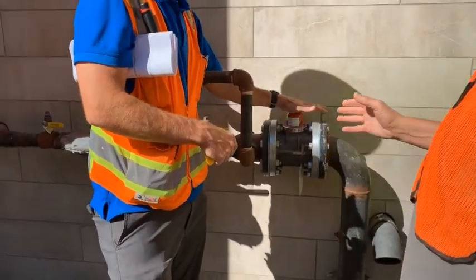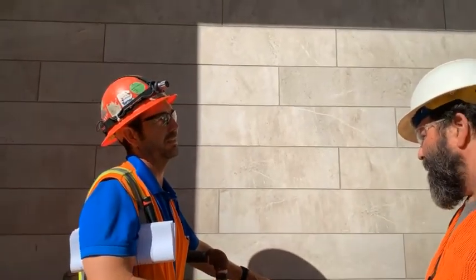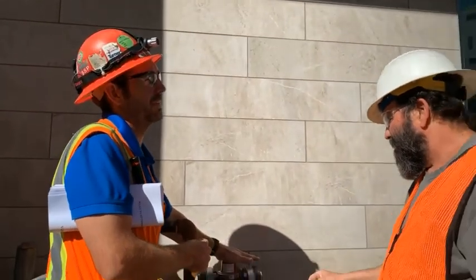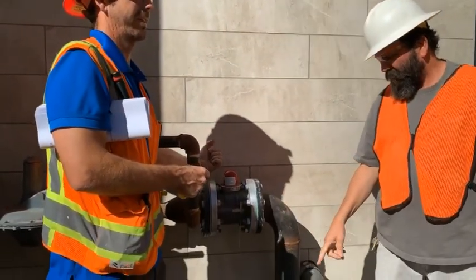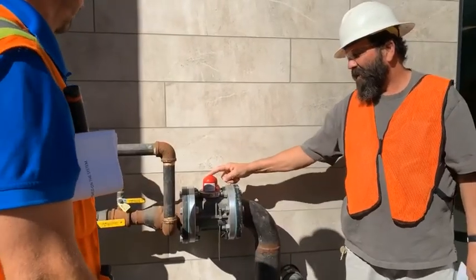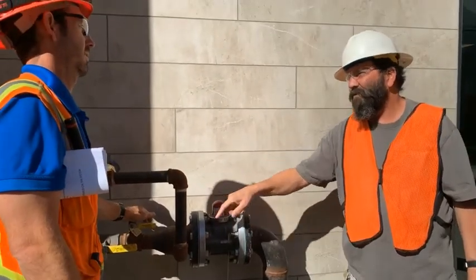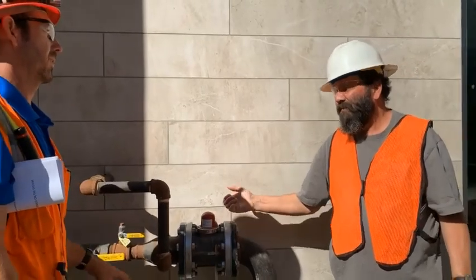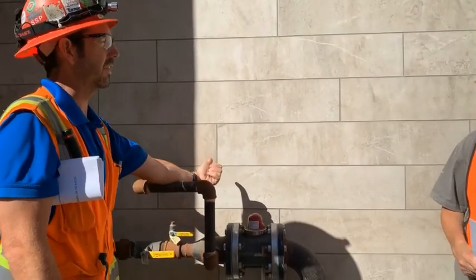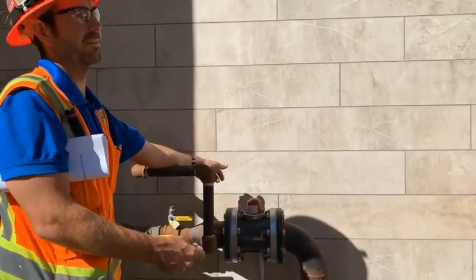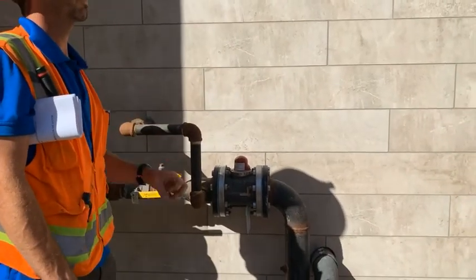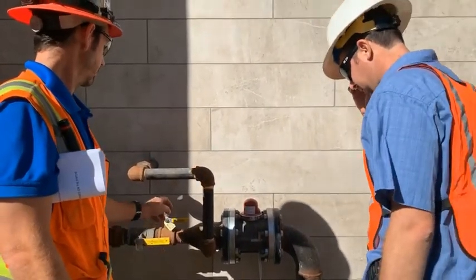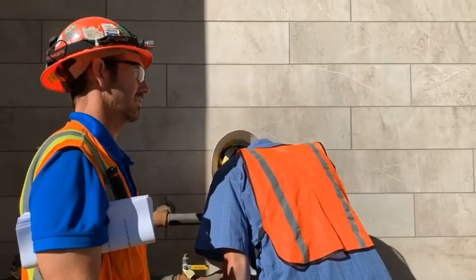Sometimes it does, but we're on the medium pressure side now, so it's still rated for the pressure, but sometimes it's harder to reset. So with that medium pressure, you shut it off, you bleed the pressure off, and then reset it. I mean, try to reset it first. If you can't, then shut off the valve. That's what I didn't understand, where to bleed the pressure. So you have to take that plug out of there. Yep, and put the plug back in, because if somebody bumps the handle.